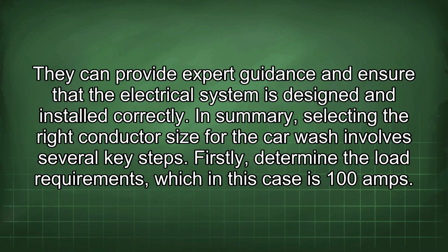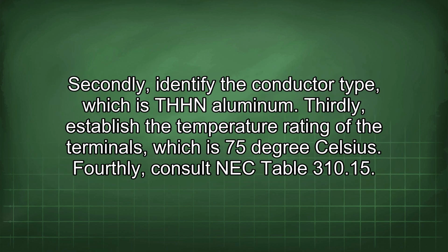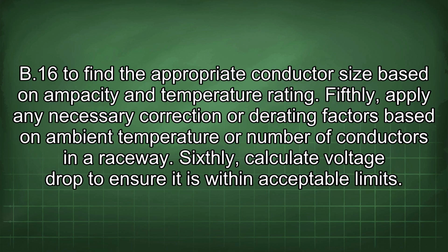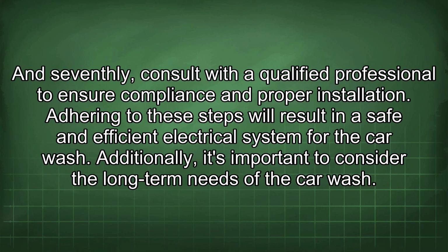In summary, selecting the right conductor size for the car wash involves several key steps. Firstly, determine the load requirements, which in this case is 100 amps. Secondly, identify the conductor type, which is THHN aluminum. Thirdly, establish the temperature rating of the terminals, which is 75 degrees Celsius. Fourthly, consult NEC Table 310.15(B)(16) to find the appropriate conductor size based on ampacity and temperature rating. Fifthly, apply any necessary correction or derating factors based on ambient temperature or number of conductors in a raceway. Sixthly, calculate voltage drop to ensure it is within acceptable limits. And seventhly, consult with a qualified professional to ensure compliance and proper installation. Adhering to these steps will result in a safe and efficient electrical system for the car wash.